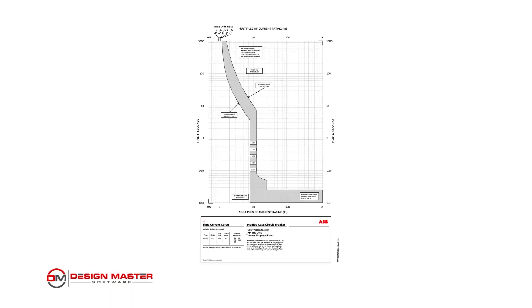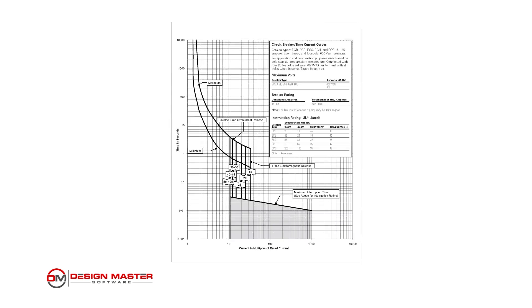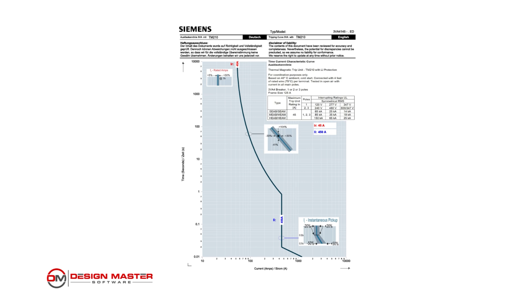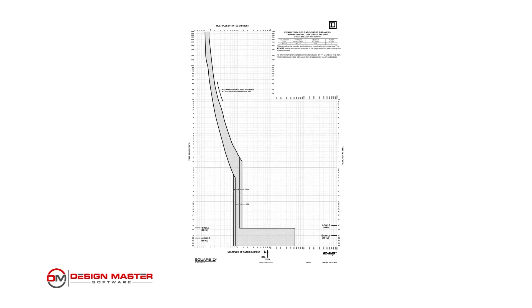Those are the three types of time current curves. Now let's look at some practical considerations when actually using them. First, realize that these curves are being pulled from analog sources — manufacturers publish PDFs with these curves and that's really the only way to get this information. Software developers have to take that PDF and digitize it by manually tracing the curves. You should keep this in mind as you use them for coordination, particularly for thermal curves and fuse curves. You don't want to have incredibly tight coordination on those, as it relies on the precision of tracing that you can't fully rely on.